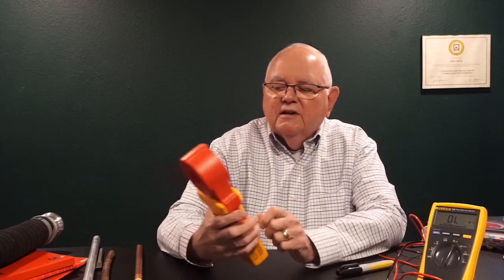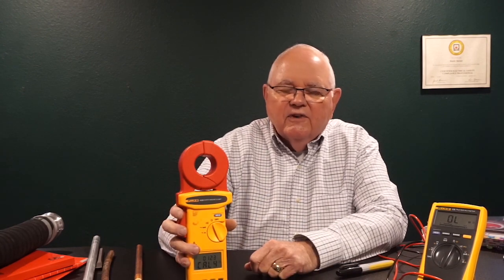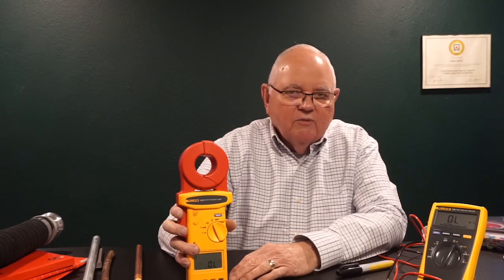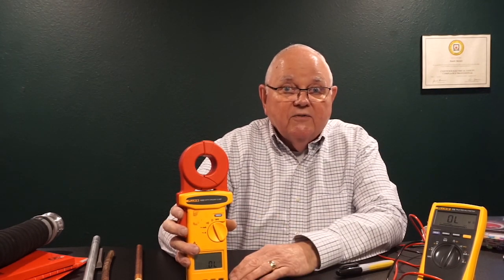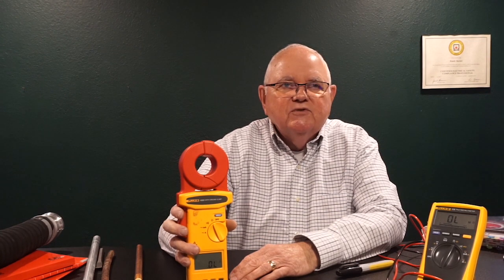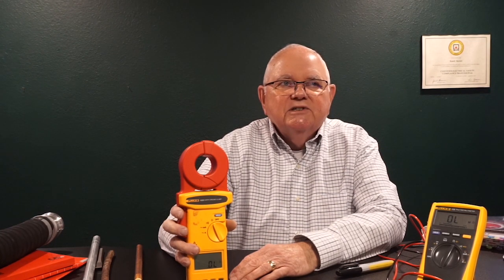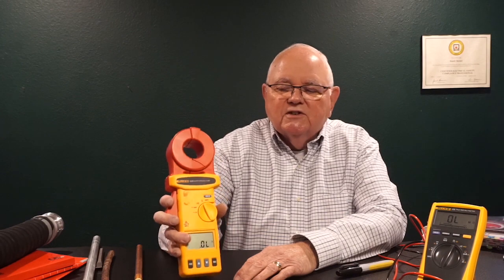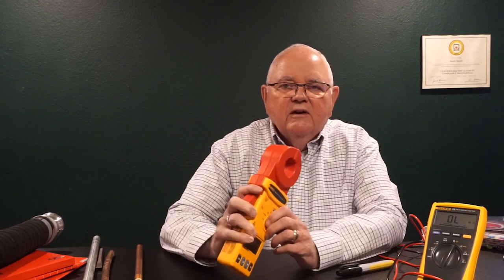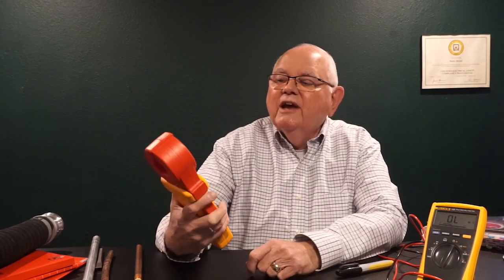And so it's a pretty handy meter. When I first turn it on, it will calibrate itself. And then after it calibrates itself, I'm ready to take a reading. Follow your manufacturer's instructions, okay? You think about it. When you read resistance, am I reading a series resistance? Or what if I'm reading parallel paths and all of that? So keep that in mind. Follow your manufacturer's instructions, depending on the type of earth resistance meter that you have, okay?